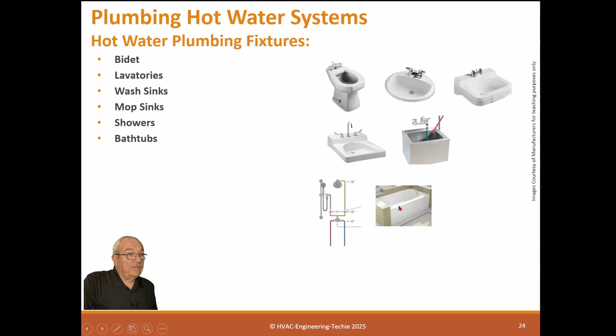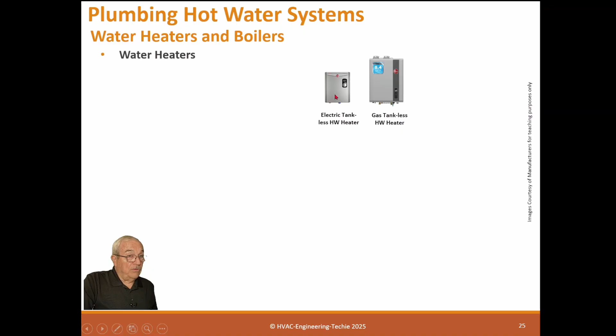Water heaters and boilers. We have different kinds of boilers. This is an electric tankless water heater, which means it has no storage tank. It's an instantaneous heater. So they have to be big enough so that the flow rate you're going to use for a shower and the flow rate you're going to use for lavatories doesn't exceed the maximum flow of the instantaneous heater, or else the water won't get hot. So they do have to be sized correctly. This is a gas tankless unit, which uses natural gas to heat. This is a tank-type electric hot water heater. This is a gas water heater, tank-type.